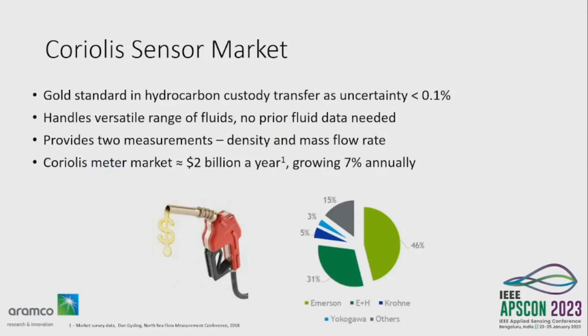Just gauging by the presentations I've seen, not many people may be familiar with Coriolis flow sensors. It is really the gold standard when it comes to hydrocarbon measurement. If petroleum is being exchanged between two parties, Coriolis flow sensors will be used because they are very, very accurate. Their uncertainty levels can be below 0.1%. Even that's sometimes quite high.